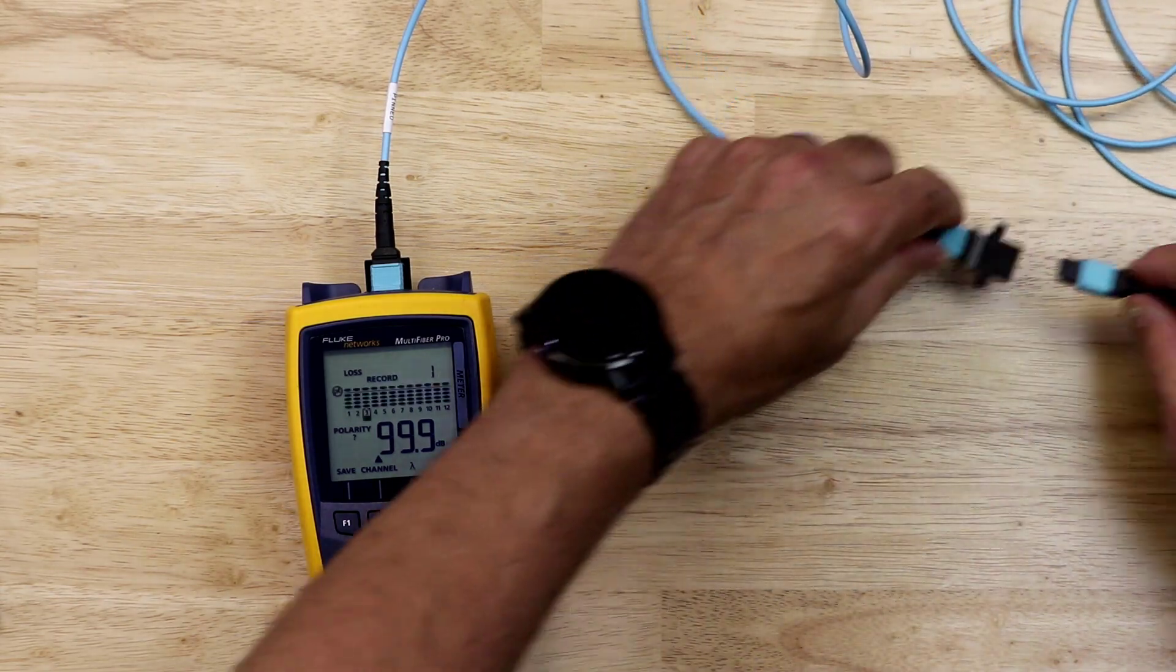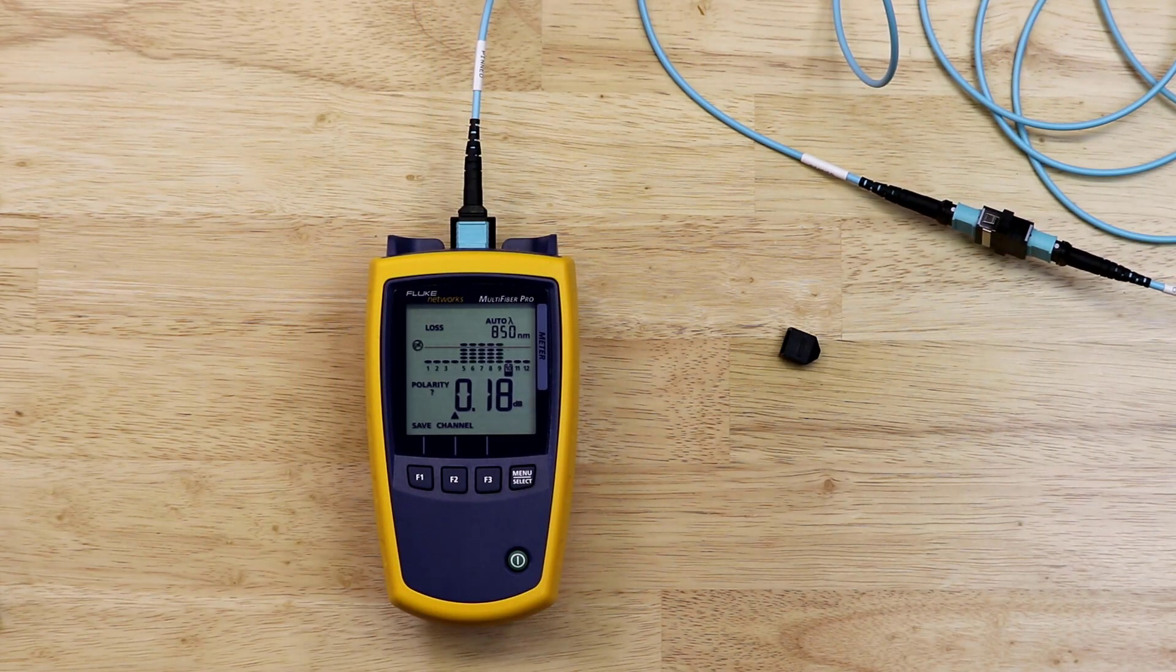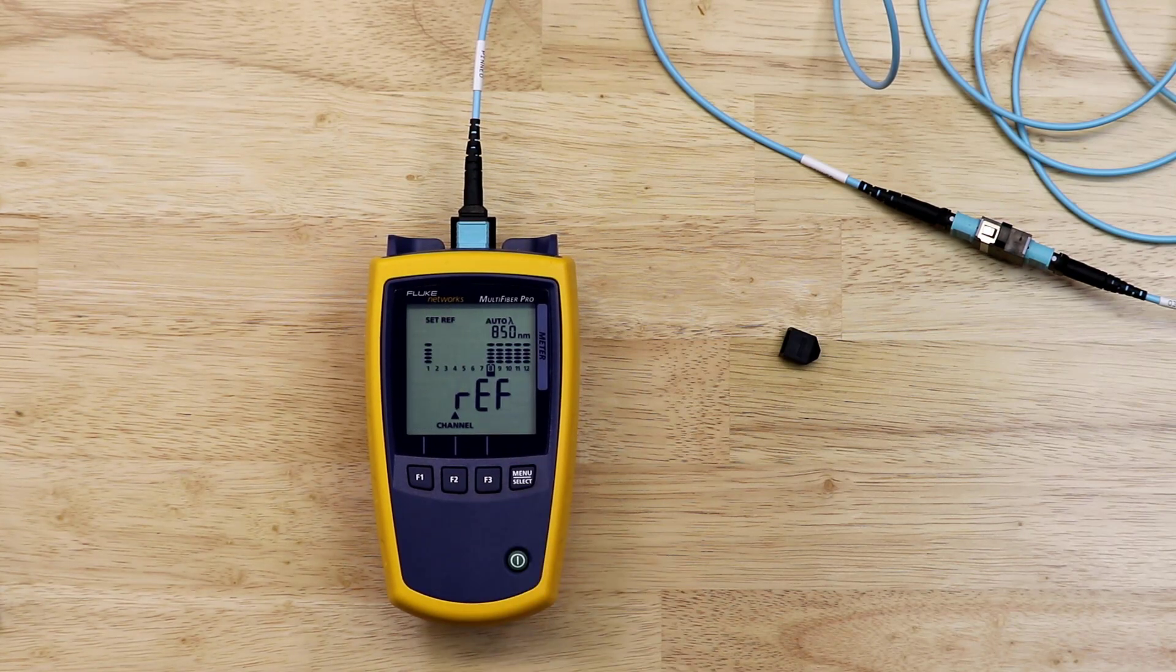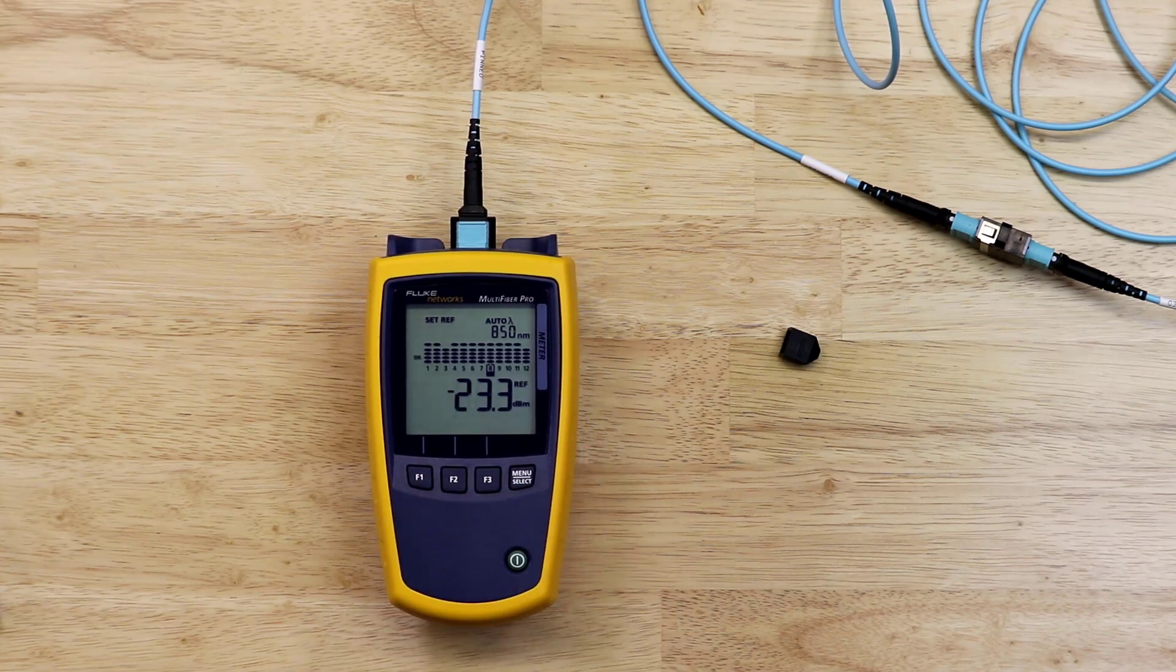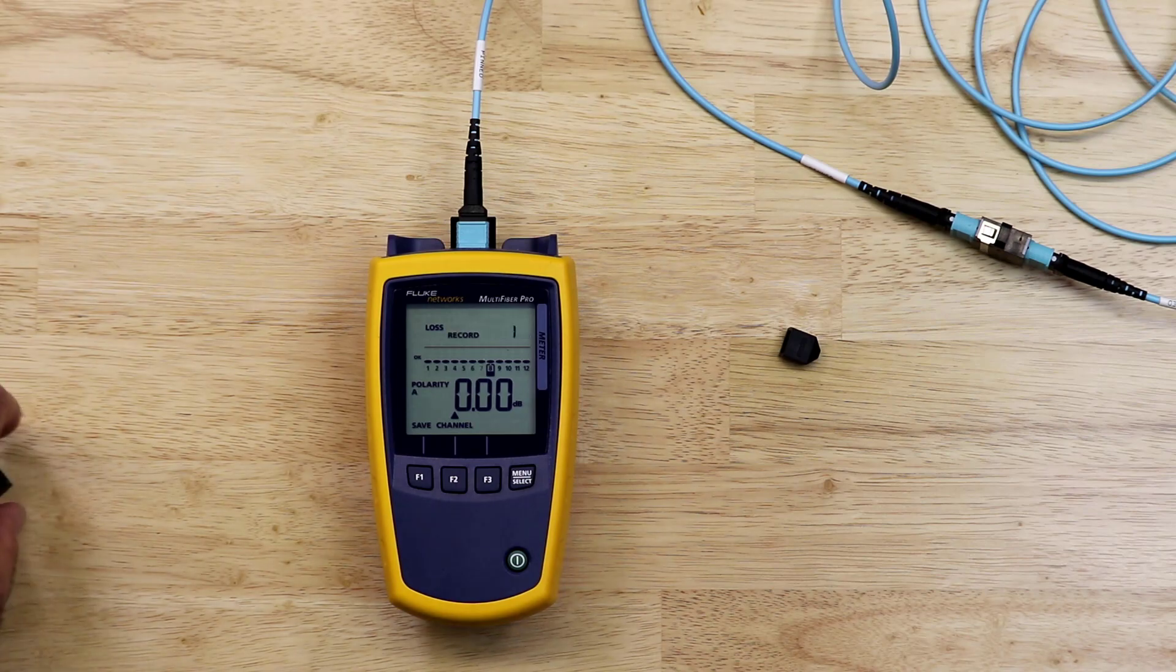After the meter has had a chance to scan all of the channels, I will make sure the loss does not exceed 0.35 dB for any of the channels. If it does, this could indicate that I have a bad test cable or the end faces are dirty. I would need to inspect the end faces. If they're good, I will need to replace the pinned to unpinned test cable. If all the loss values are less than 0.35 dB, I press the menu select button until I see set reference on the screen. Referencing will begin automatically. After the referencing process is complete, I will press save to zero out my measurements and save the second reference. I have now referenced out both of my test cables.